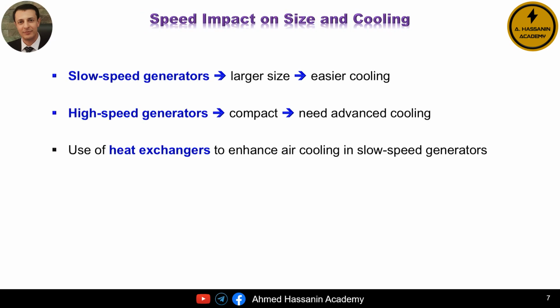All right, now let's see how speed changes the picture when it comes to generator size and cooling. First, think about slow-speed synchronous generators. These machines are usually larger in physical size compared to high-speed generators with the same power rating. That larger size actually works in our favor because it gives us more surface area for heat to escape. As a result, cooling becomes easier, and in many cases we can rely on air cooling, supported by heat exchangers that push ambient air through the generator body.